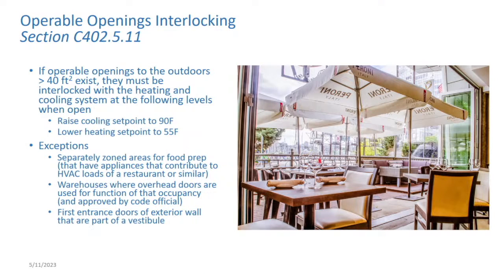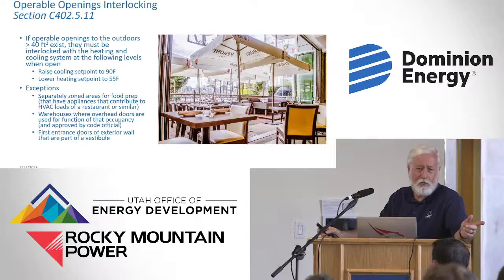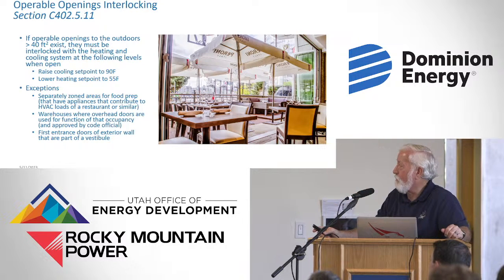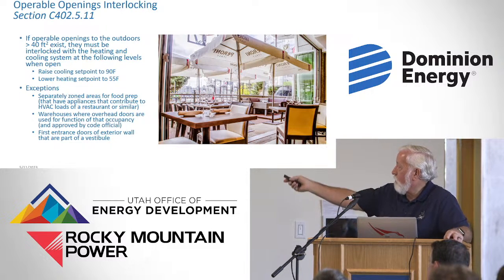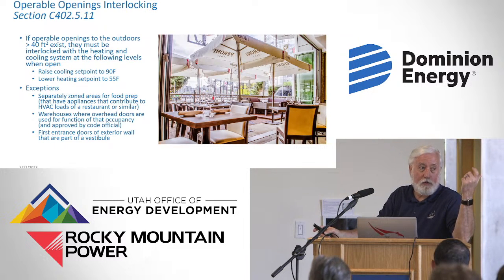Here's our operable opening interlocking. And it's in two sections in the code. It's in the envelope and it's in the mechanical. If the door is greater than 40 square feet, that's not a very big door, it must be interlocked with heating and cooling at the following levels when it's open. Raise the cooling set point to 90, lower the heating set point to 55, and we have some exceptions there. But generally, most restaurants are going to have to meet this. I doubt this is a control that you guys will sell. It's going to be a control that the HVAC suppliers will provide. It's basically going to have to be a door switch that triggers a setup or set down, depending on if we're in cooling or heating mode.